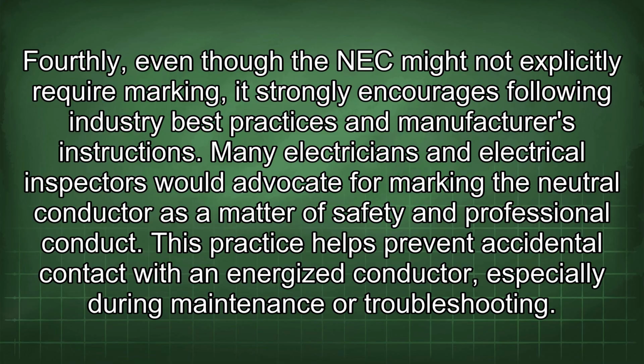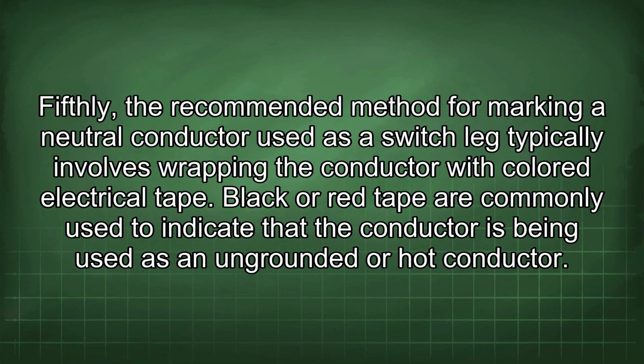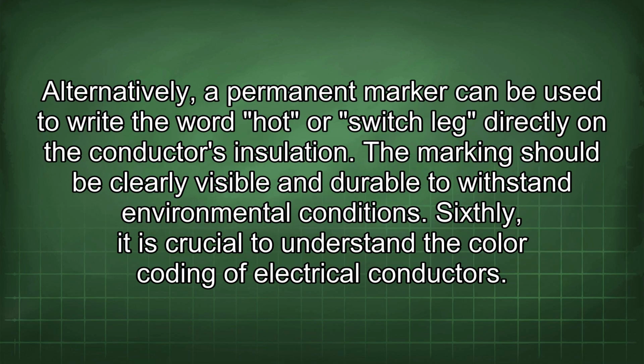This practice helps prevent accidental contact with an energized conductor, especially during maintenance or troubleshooting. Fifthly, the recommended method for marking a neutral conductor used as a switch leg typically involves wrapping the conductor with colored electrical tape. Black or red tape are commonly used to indicate that the conductor is being used as an ungrounded or hot conductor. Alternatively, a permanent marker can be used to write the word hot or switch leg directly on the conductor's insulation. The marking should be clearly visible and durable to withstand environmental conditions.